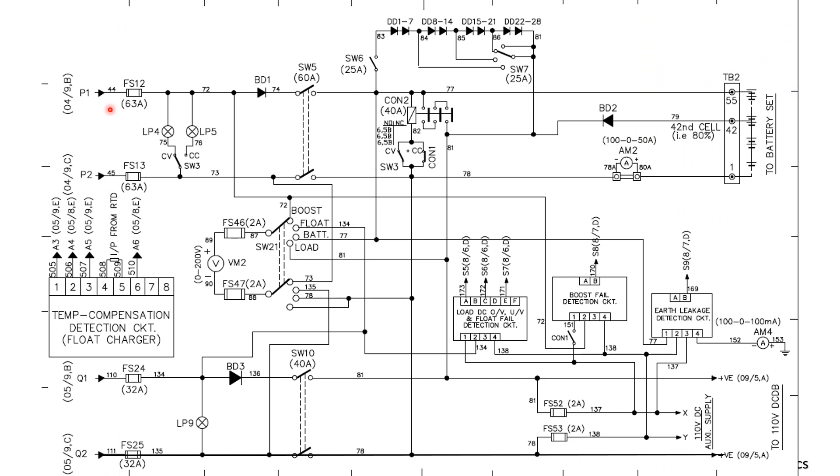Our DC is coming through P1 and P2, through the fuse, and through the boost it is going to the battery set. In case the float charger is off and only boost is on, we can also supply to the control panels through BD2, which is a reverse blocking diode. BD2 is connected to a tap cell — the 42nd cell — and the voltage across this will be sufficient to supply 110 volts DC to the DC DB or to the control panels.